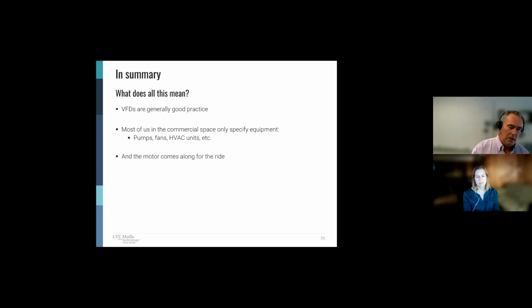I know several pump station operators, they have VFDs on all of their pumps, and rather than run one pump at 100% and one pump at 80%, you know, they run them both at 90% because they like to say that it increases the longevity of the pumps. Okay. Also gives them total control. Now, the advantage that we have, or some of us have in the commercial space, is we typically specify equipment, not motors. We're going to call up our favorite HVAC vendor and say, I need an air handler that provides 30,000 CFM at this static pressure, and I want to be able to control it because it's going to be a variable volume system, and you don't worry about what motor they put on it.